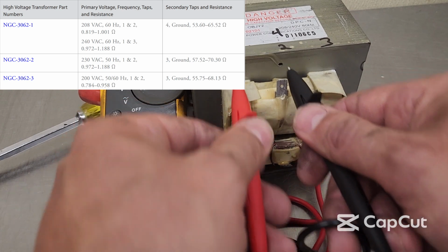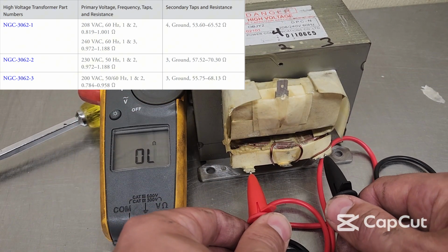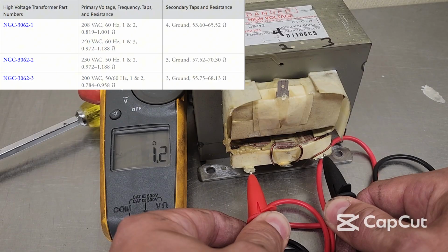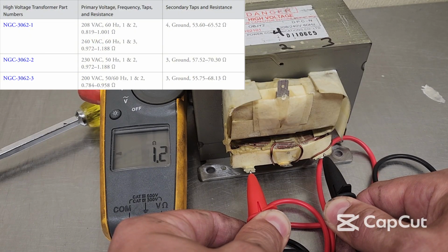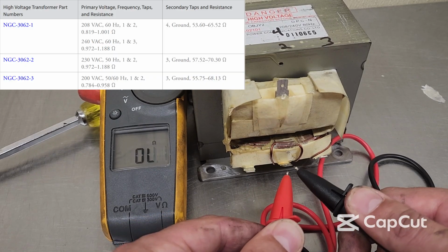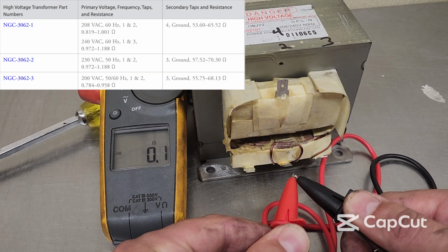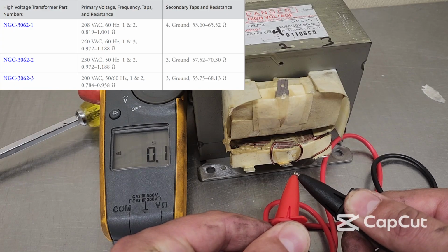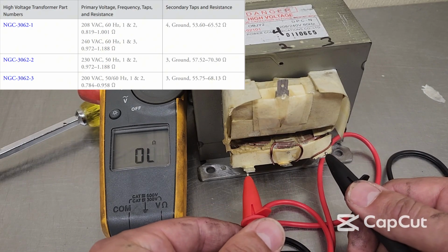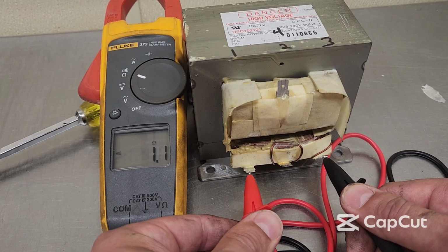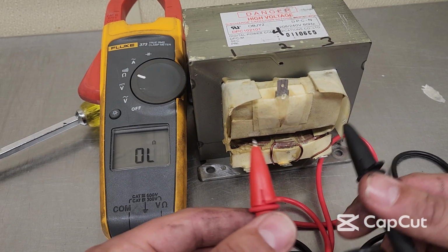So 1 and 2, and then 1 and 3 is your 240 volt tap, and that will be between 0.972 ohms to 1.188 ohms. In this case, we would subtract 0.1 off because of our leads being 0.1 ohms. So we take that 0.1 off, and that puts us well within our specifications. Hopefully that helps you out.